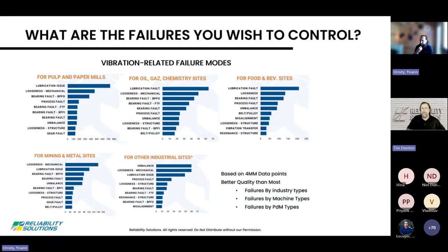And if we were lubricated and we did have grease in the bearing, where did the grease go? How can the lubrication run out? Where does it go? Oh, let me see. If the machine's misaligned, I kill the seals and then the lubricant escapes. Over-greasing, absolutely. And we get into the habit of over-greasing because we keep losing all of it.